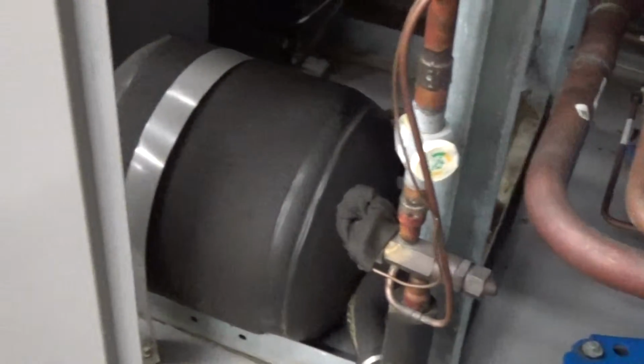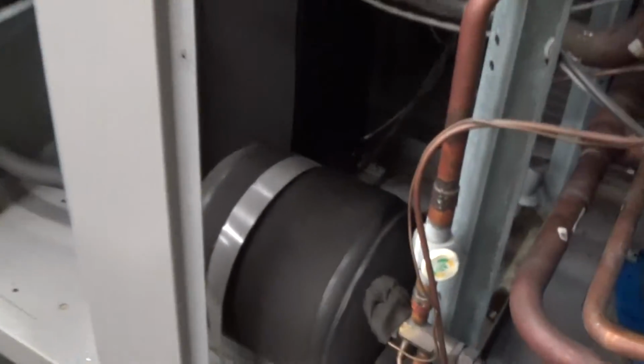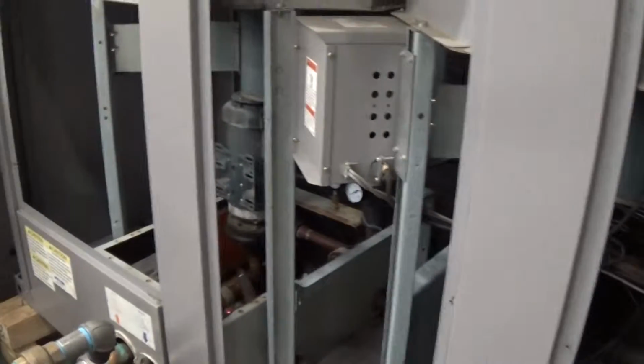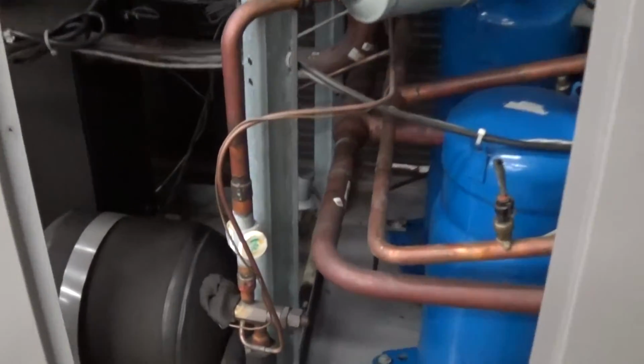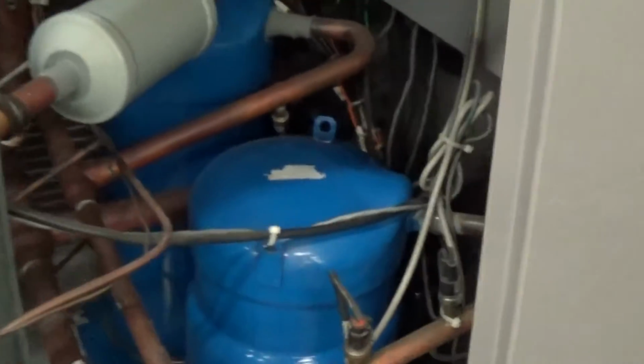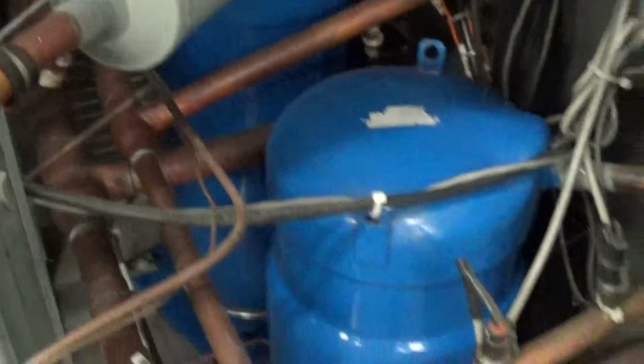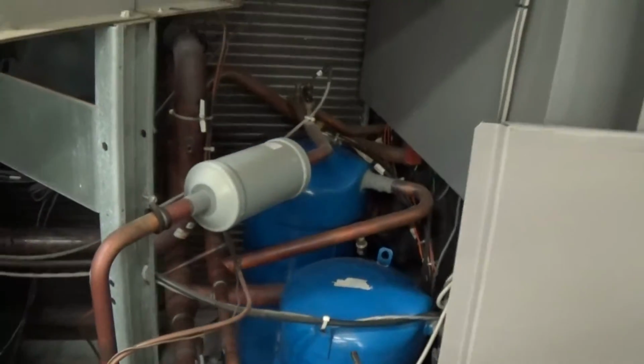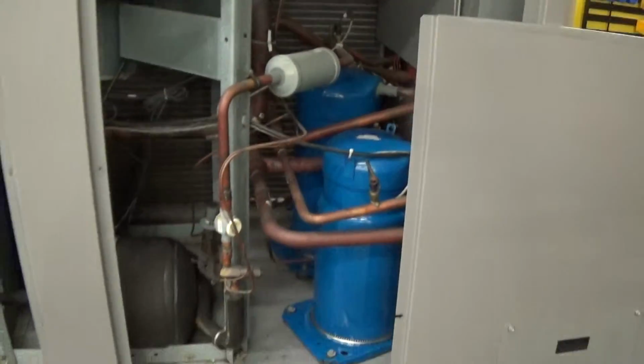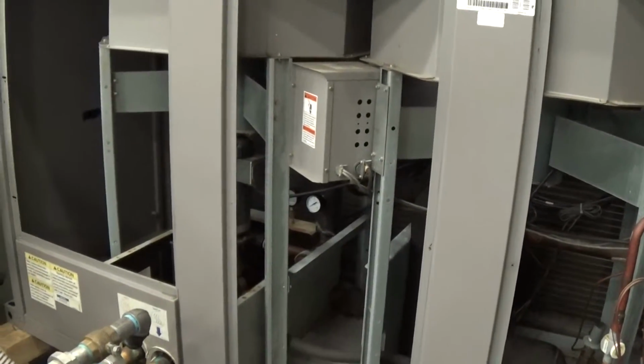We also have an expansion tank in this unit here, although for the way you're going to pipe the fluid for the glycol solution for the brewery, it's probably not going to be needed. We have our sight glass. Where did we go here? Oh, we have our sight glass for the refrigerant viewing there once it gets underway. Our thermo expansion valve, and this unit does have a hot gas bypass for additional minimum capacity control. It is a single circuit system, as you can see by the compressor, the refrigerant piping for the compressors there. But it is a dual compressor system. If one compressor does go down, you can disable the other and run it as just a single compressor unit.